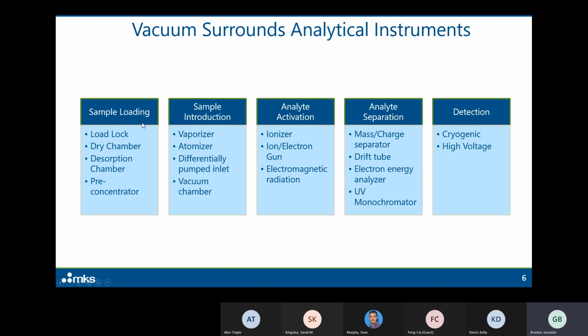So we start with sample loading. The sample loading section of an analytical instrument is where the sample is presented to the instrument. This could include a load lock. For example, say you're doing a MALDI-TOF experiment where you have to load in a chip with a bunch of matrix-embedded protein samples. You will have a load lock, which is a little chamber. It will have a load lock gate, which will open and expose that chamber to atmosphere. That gate will close. The chamber will be pumped down. And when the pressure is low enough, another gate will open and will allow you to enter that chip into the vacuum system. Typical load lock operation.